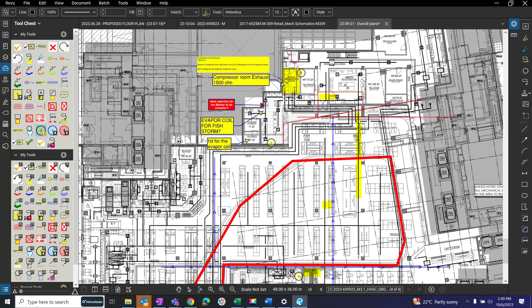Okay, that's good, we'd need to know that too for programming purposes for the controller. Do you know the maximum amount? I know we can do one set, we'd probably take the bigger one. I don't think we could take multiple, especially when there's no BMS. When there's a microthermal system, they can do the math and tell us, but without that it's a little simpler. We might just pick the bigger of the two. And of course we've got to make sure we never get below your IAQ requirements, since sometimes you don't have this latitude because you need the ventilation for other reasons. But definitely we should look at it.